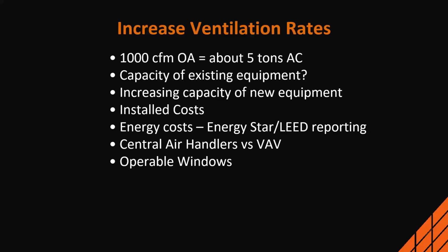If we have a central system, we have to look at how I actually get that ventilation to the space. If I have a single zone system, I bring air into the unit and it goes to the space. If I have a VAV system, now I have a damper downstream of that unit that's going to vary the amount of air going to my space. So we have to look at control strategies to make sure we keep those VAV boxes open as much as possible. And there are 2 scenarios. One is you increase the minimums, which can lead to some overcooling and some reheat running, which again eats up a little more energy.